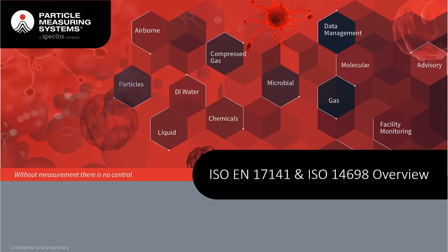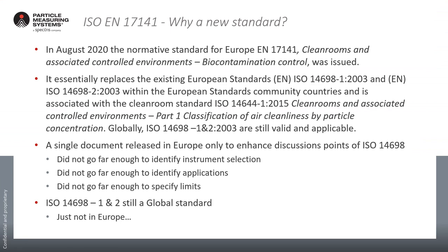Today's presentation is on ISO European Normative 17141 and how it compares to ISO 14698. In August 2020, the normative standard for the European norm EN 17141 Clean Rooms and Associated Controlled Environments Biocontamination Control was issued, and it wasn't brought into effect until April 2021. It's a relatively new standard and it essentially replaces within the European standards community ISO 14698 part one and ISO 14698 part two.